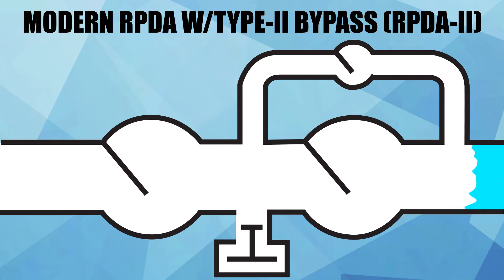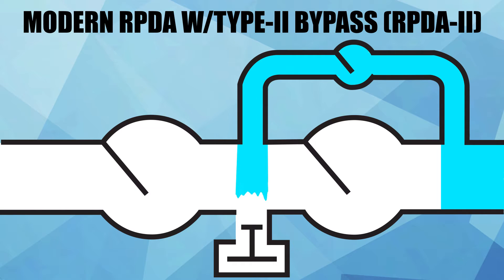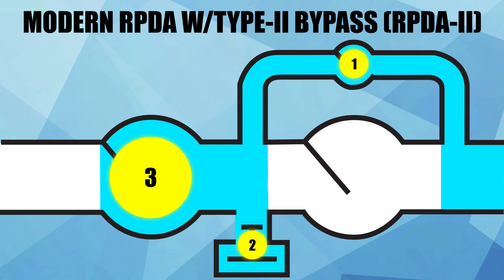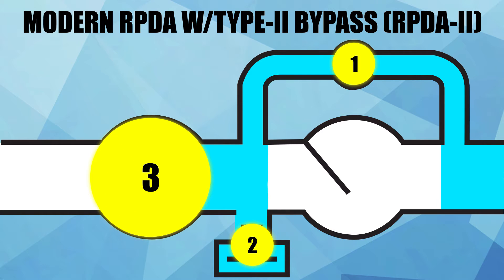During a backflow condition on a modern RPDA with a Type 2 bypass, the water first encounters the bypass single check. Next, the water encounters the main valve relief valve. And then the water encounters the main valve first check. This also provides three mechanisms of backflow protection.